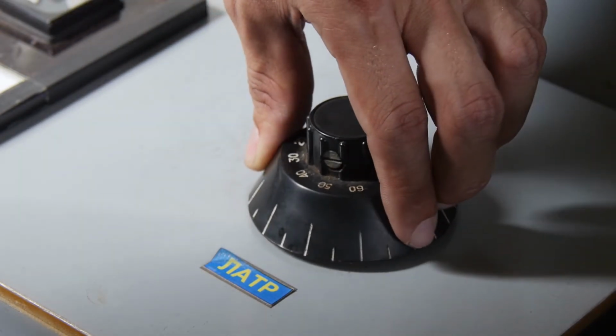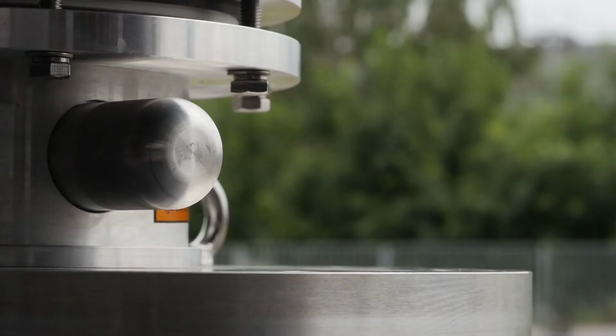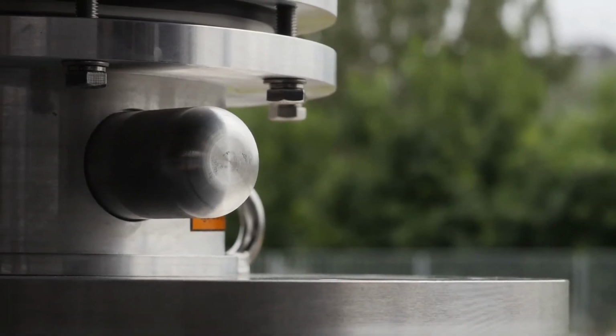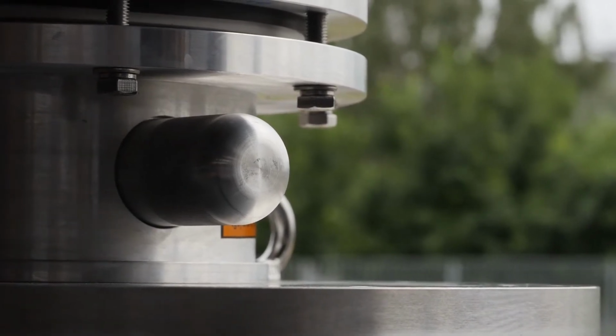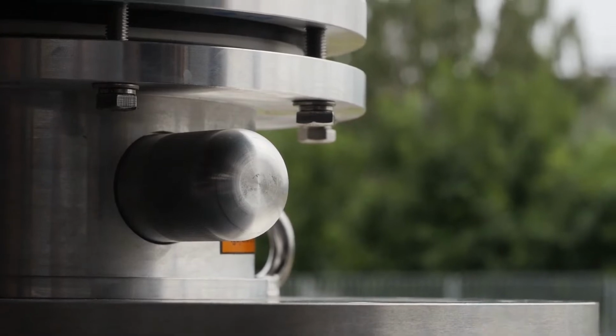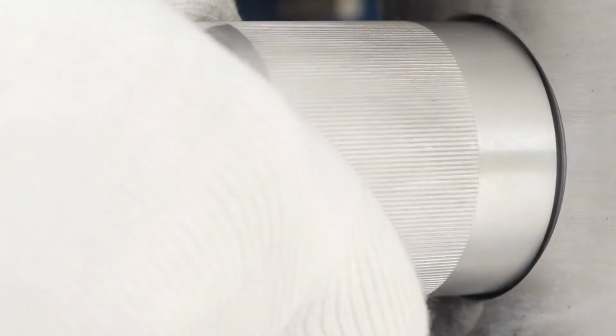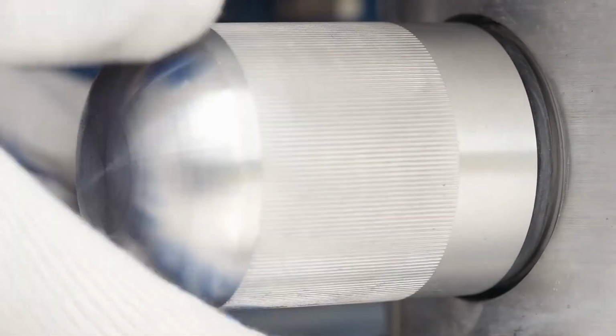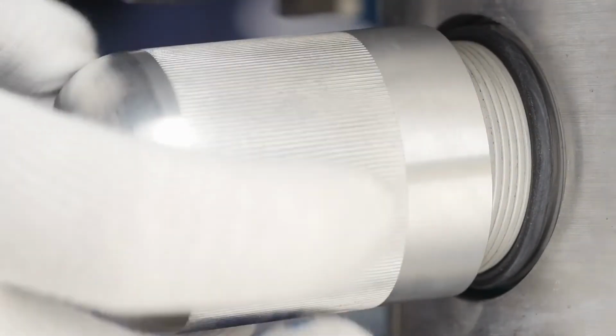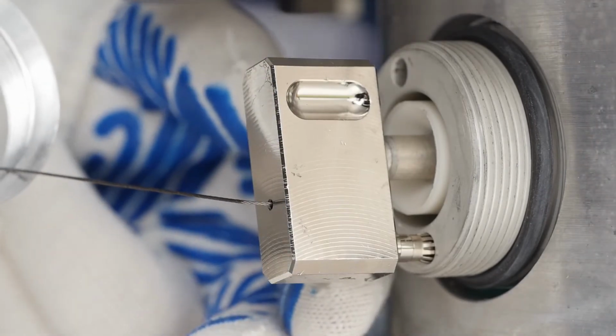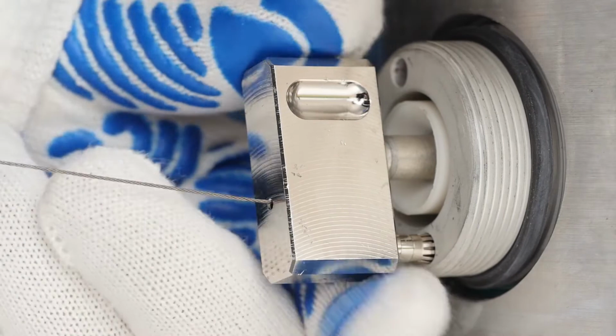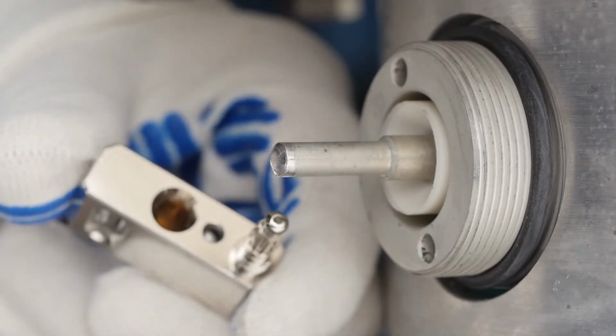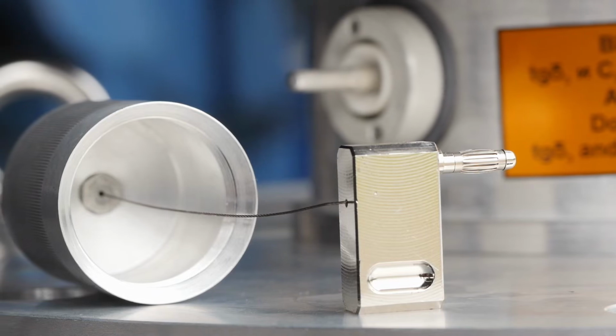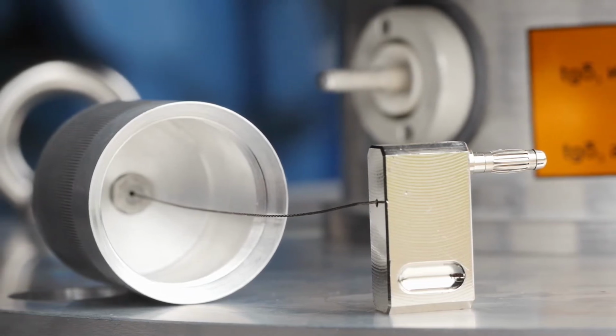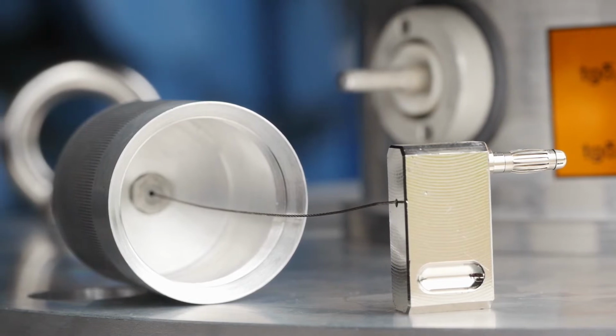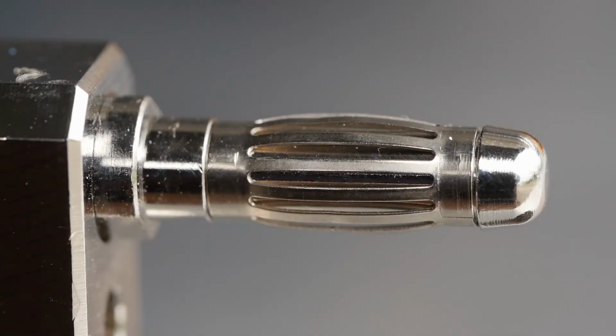Values of capacity and dielectric loss tangent achieved during acceptance testing are given in the bushing certificate. Let us consider such an important procedure as the correct grounding of the test tap. Grounding shall be made using a special multi-contact connected to a test tap hood with a wire. The hood ensures tightness of the test tap cavity and protection against mechanical damages, whereas the wire prevents loss of the grounding multi-contact. To unground the test tap, unscrew its hood and remove the multi-contact off the test tap pin. It will ensure the test tap ungrounding and the possibility of internal insulation measurements.